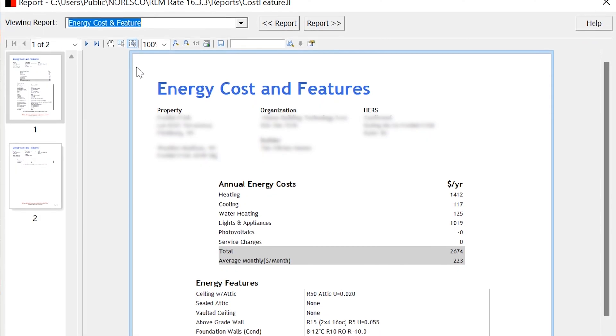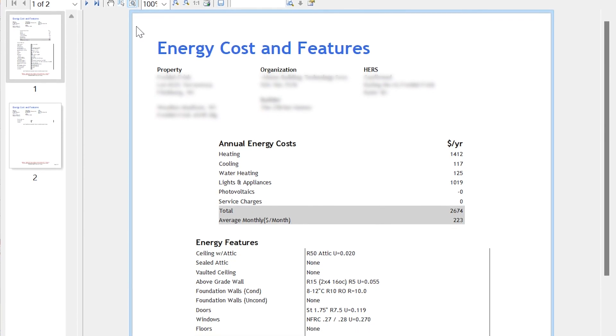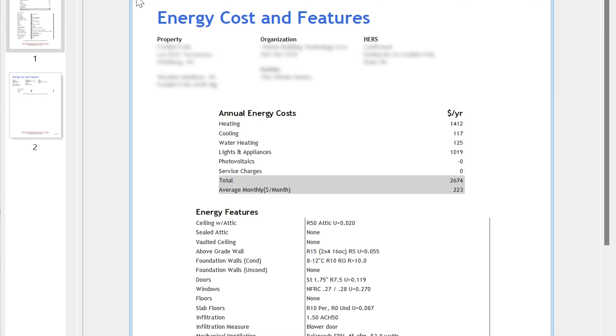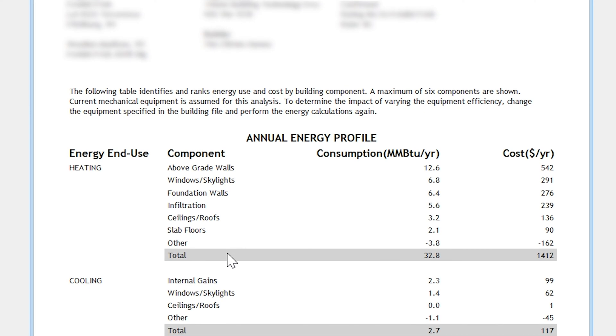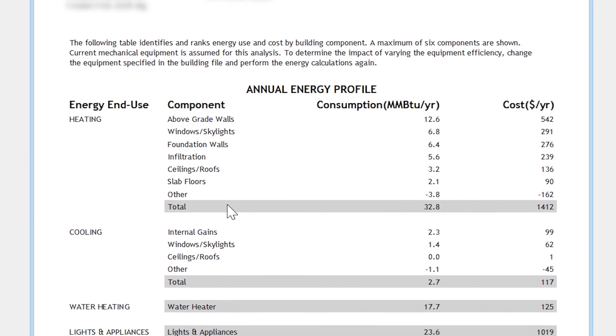We can run what's first called an energy cost and feature report based on what they gave us for plans and what they initially wanted to use for insulation and mechanicals. The only thing we have to estimate up front is the air tightness of the building — we can't get that off a drawing, but we've got enough experience with over 50,000 homes that we've tested, so we have a pretty good idea. The software will actually estimate the operating costs for heating, cooling, hot water, lights, and appliances. From there, the software can go to an action report and take the heating bill and break it down in pecking order. Something has to be the largest contributor to the heating. If you can't identify those up front, you might spend all kinds of money on items that are way down on the bottom of the list, having the least potential benefit but adding a lot of cost to the building.